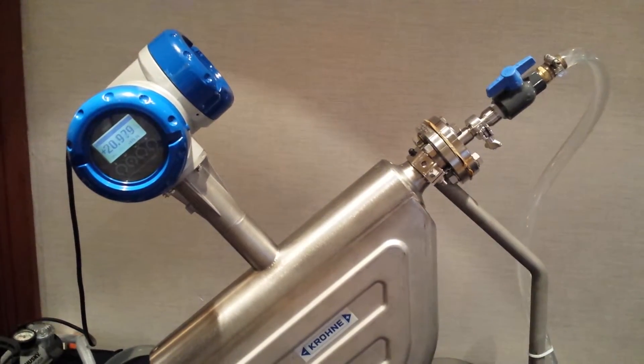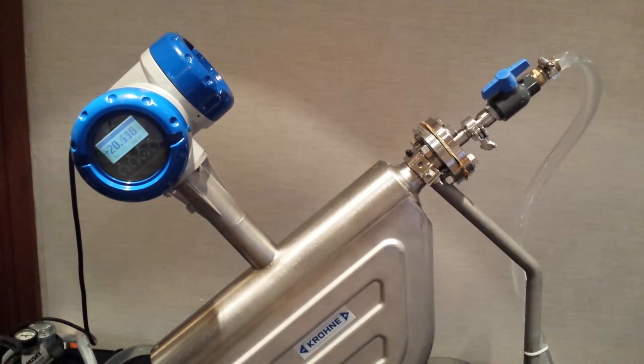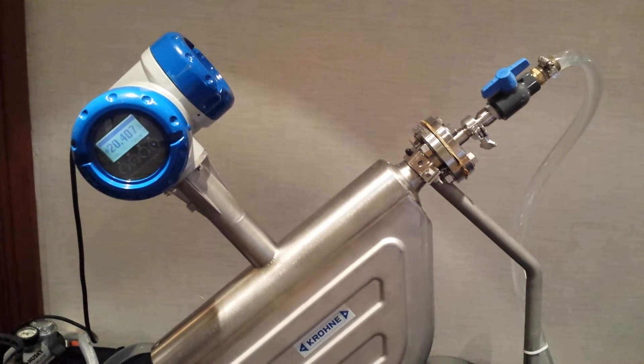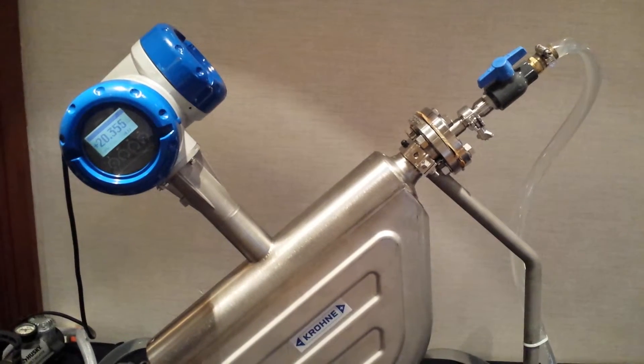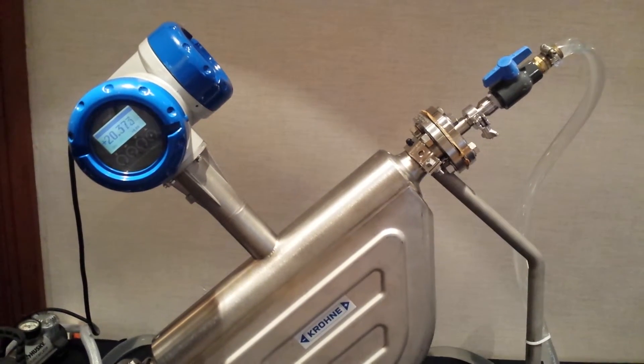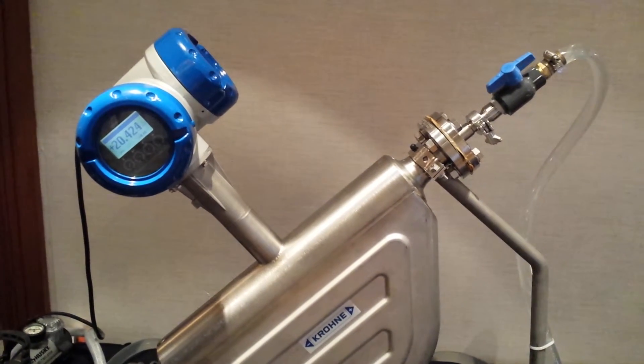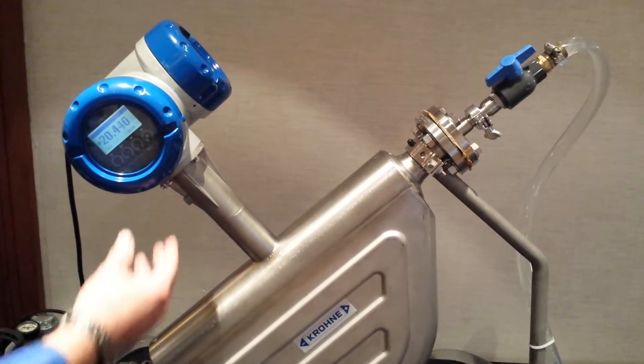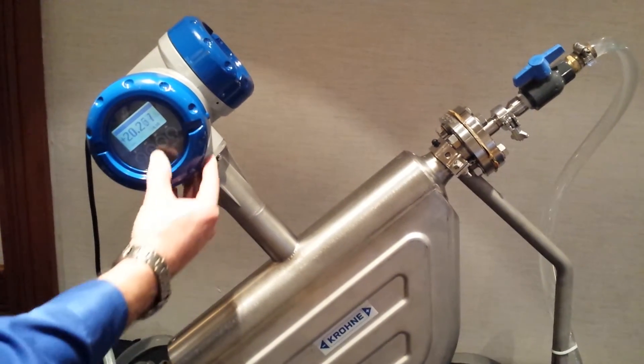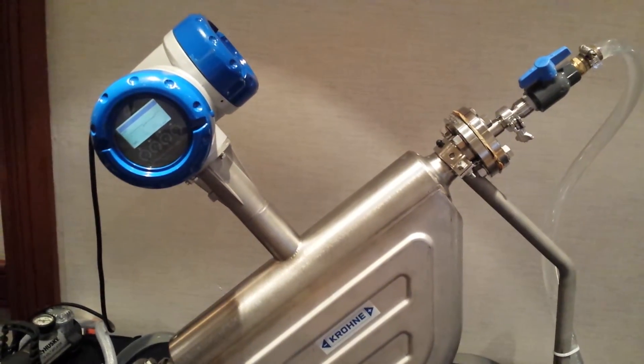Get back to normal, all water, no air. Flow rate's back to 20 pounds per minute. We're in volumetric flow, liters per minute. Two-phase flow is back to zero and density is back up.